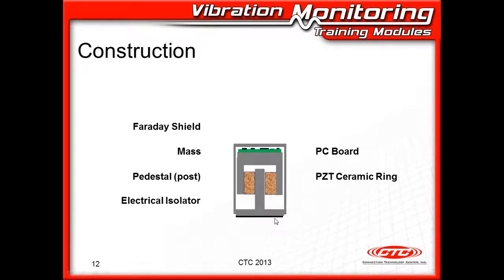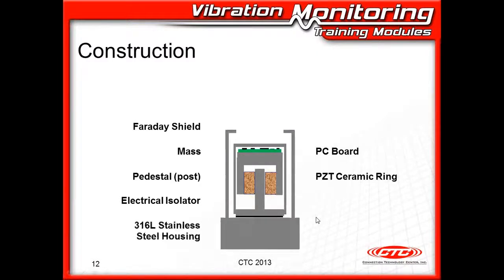We also are going to put in an electrical isolator down here on the bottom because we don't want to form a ground loop here. So we're going to have an electrical isolator on the bottom of this sensing element. Then we'll pull in our 316 stainless steel housing. We're using an L version of 316 because it makes it weldable. We've now got a good solid chunk of steel or stainless steel around our sensing element, providing protection. We'll put our 1/4-28 threads in here, and we can have any number of adapter studs, M6, M8, M10, off this 1/4-28 base.